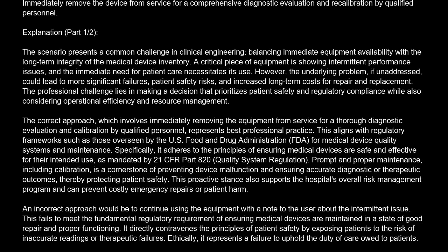and resource management. The correct approach, which involves immediately removing the equipment from service for a thorough diagnostic evaluation and calibration by qualified personnel, represents best professional practice. This aligns with regulatory frameworks such as those overseen by the U.S. Food and Drug Administration, FDA, for medical device quality systems and maintenance. Specifically, it adheres to the principles of ensuring medical devices are safe and effective for their intended use, as mandated by 21 CFR Part 820, Quality System Regulation.